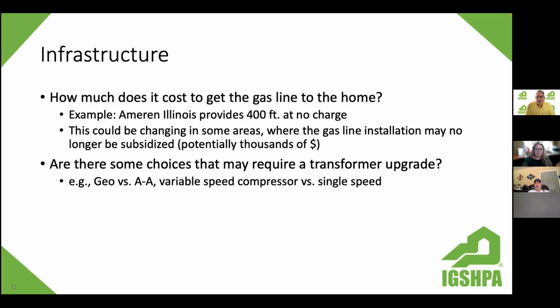There are some cases, I've seen this in the past, where a transformer upgrade might be required. So, is that going to be something the consumer pays for, or does the electric utility pay for that? It kind of depends on the area. But it might be that geo, with its lower demand, is not going to require the upgrade. Air source heat pump might. There's some factors there we could look at.